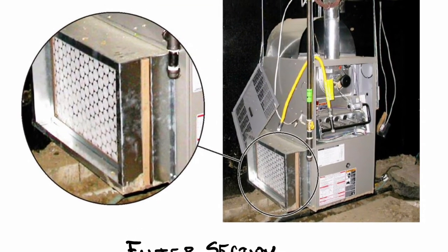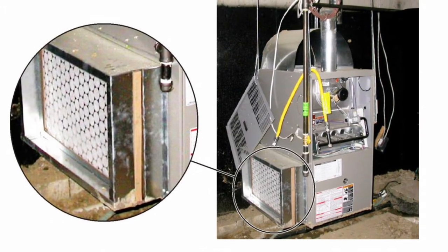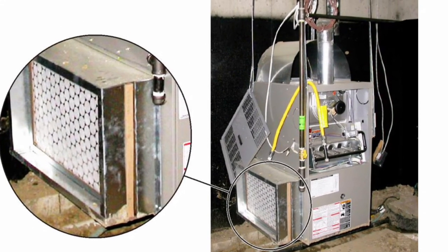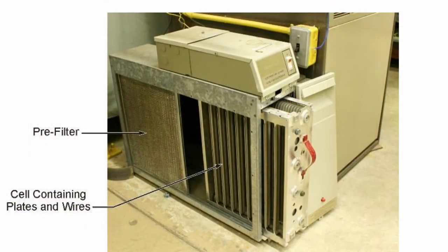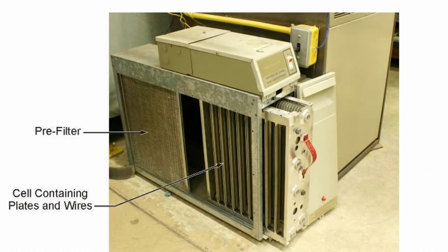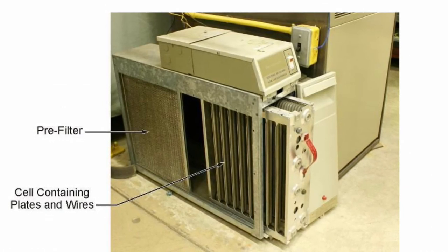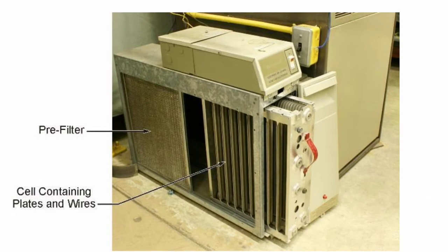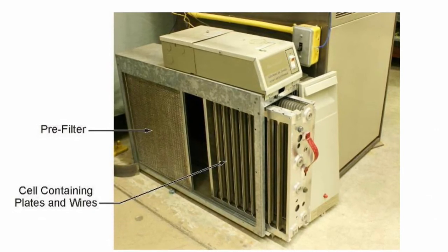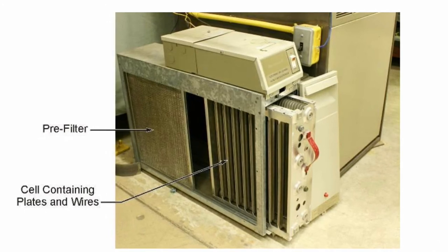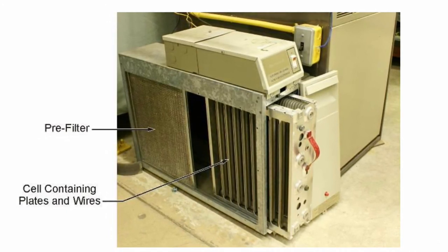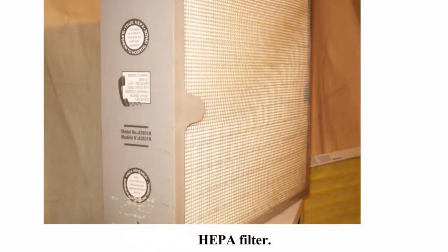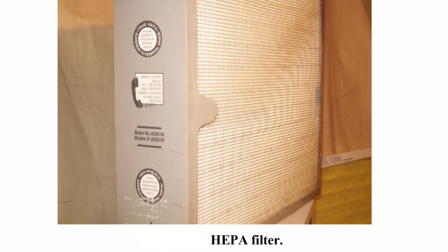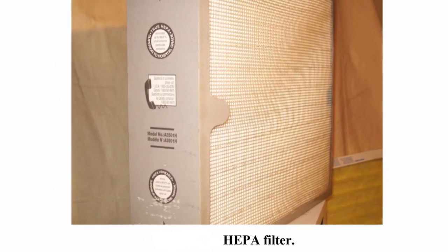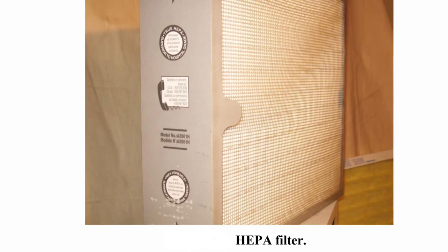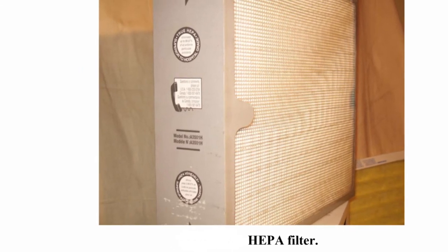This picture shows you a disposable filter installed in a metal rack on the return side of the furnace. This is an electronic air cleaner. These air cleaners have the ability to remove particles much smaller than fibrous media filters. This air cleaner requires regular maintenance to remove most of the particles that have been attracted to collector plates inside the electronic air cleaner. The last filter is the HEPA, High Efficiency Particulate Air filter, which may be considered the most efficient throwaway filter.